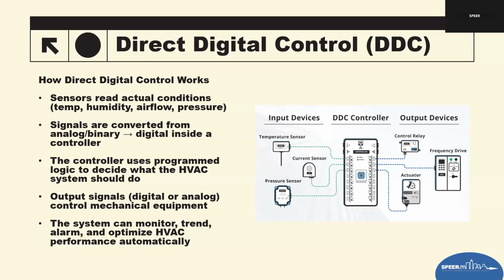Such as, should we be heating or cooling, or should we be adjusting ventilation? Should we also change damper position? Then the controller decides. The output signal controls the equipment. The controller converts digital commands back to analog or binary. These operate the physical equipment: the VAV dampers, the valves, the fan speeds, the economizers, the compressors, and so on. The system can monitor trends and alarms. It can optimize performance. So this is the big benefit of DDCs. It allows continuous monitoring, trend logs, performance analysis, alarms, and optimization.